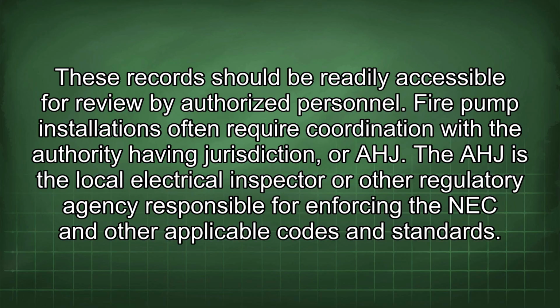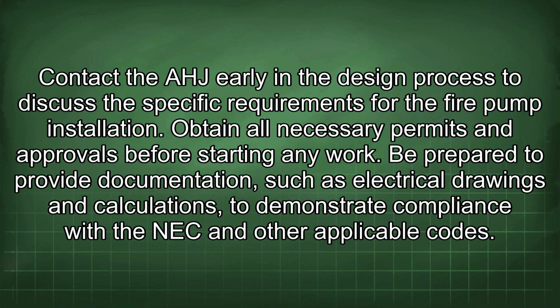Fire pump installations often require coordination with the authority having jurisdiction, or AHJ. The AHJ is the local electrical inspector or other regulatory agency responsible for enforcing the NEC and other applicable codes and standards. Contact the AHJ early in the design process to discuss the specific requirements for the fire pump installation. Obtain all necessary permits and approvals before starting any work. Be prepared to provide documentation, such as electrical drawings and calculations, to demonstrate compliance with NEC and other applicable codes.